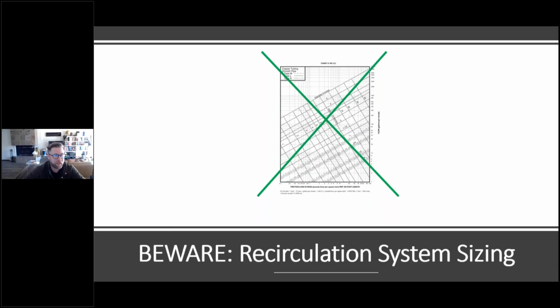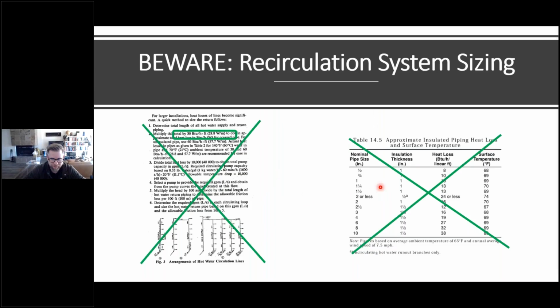The other thing we need to eliminate is some old design techniques, one of which is utilizing, as you can see here, I'm highlighting with this box, a 30 BTU per hour per lineal foot heat loss throughout the whole system. Do not use that. And I'll show you why, but in essence, you're going to end up with a system that's grossly oversized. Now, this chart on the right shows BTU losses based on a couple insulation thicknesses. And I have an X for this.